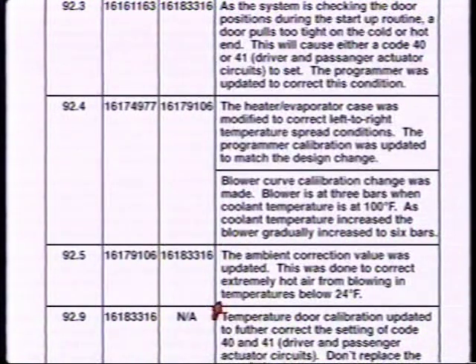The ambient correction value was updated in the 92.5 programmers. This was done to correct complaints of extremely hot air being blown out of the outlets when the heater was on and the ambient temperature was below -24 degrees Fahrenheit. This usually only happens in extremely cold climates.